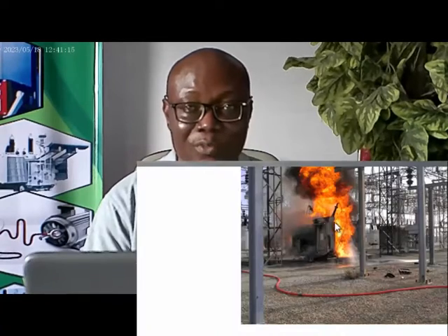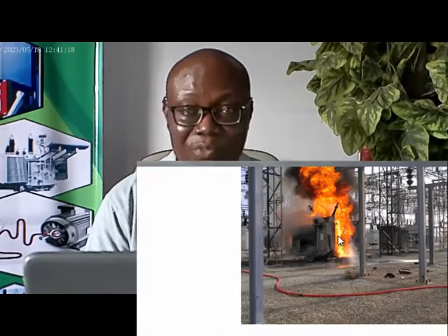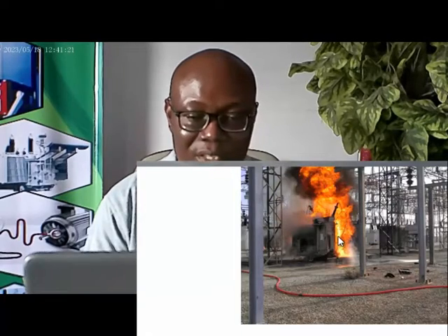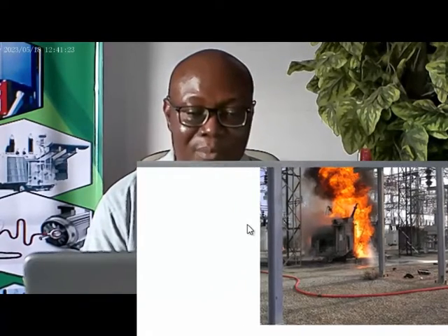Phase-to-phase shorting can also result from poor insulation, and the result of that will be fire and explosion. The equipment can malfunction and eventually fail once there is insulation failure, a drop in the insulation value of the equipment. So you see that insulation testing your equipment to get the actual insulation value is very, very important to the operation of your electrical asset.